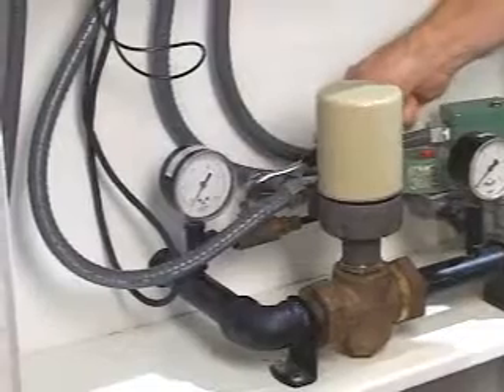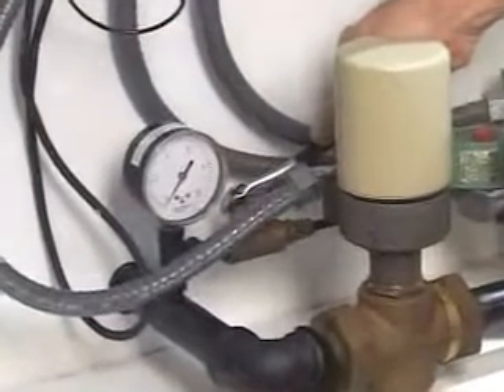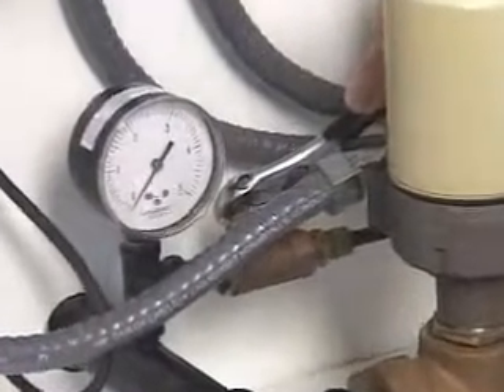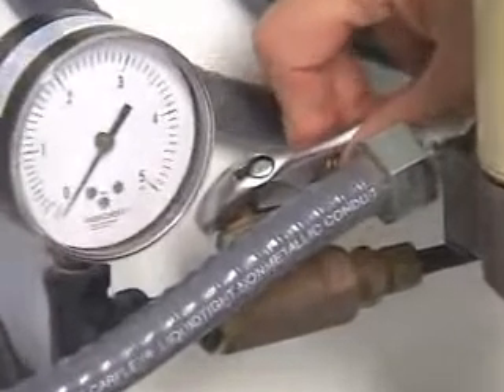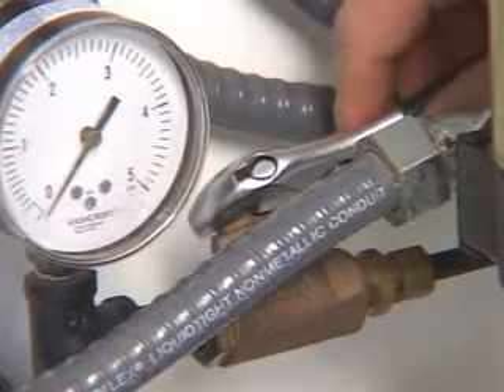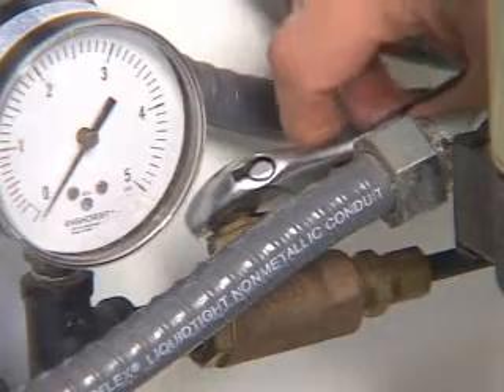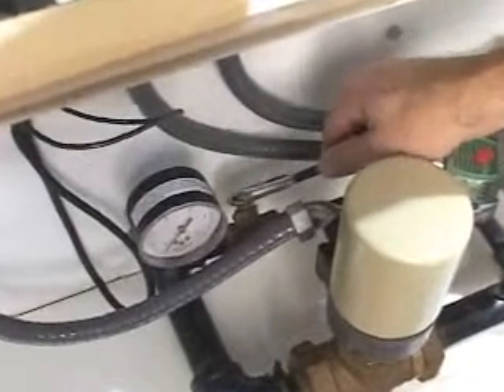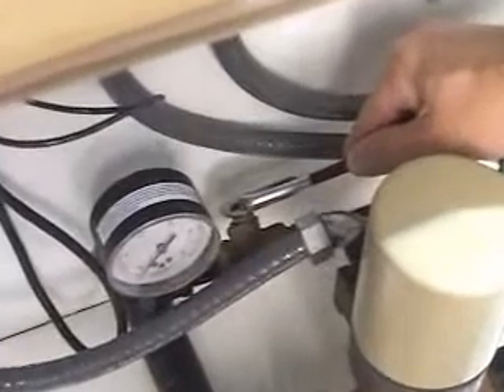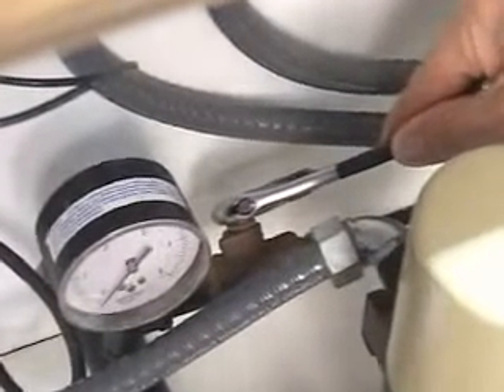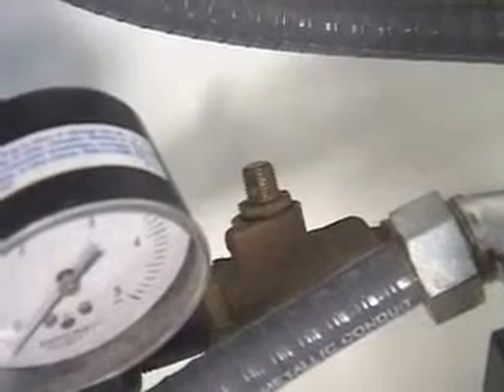Second, note the 3/8-inch ball valve behind the main gas valve in the lower cabinet. This is the low fire adjustment. This valve should be open only enough to allow the burner to light reliably each time it is started, and no more. Use a pair of pliers or a small wrench to adjust it. If it is open too much, the warm-up air will be too hot coming from the unit. This wastes fuel and damages equipment.